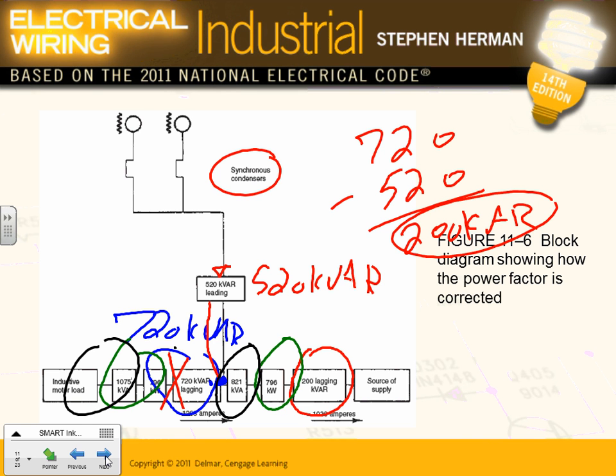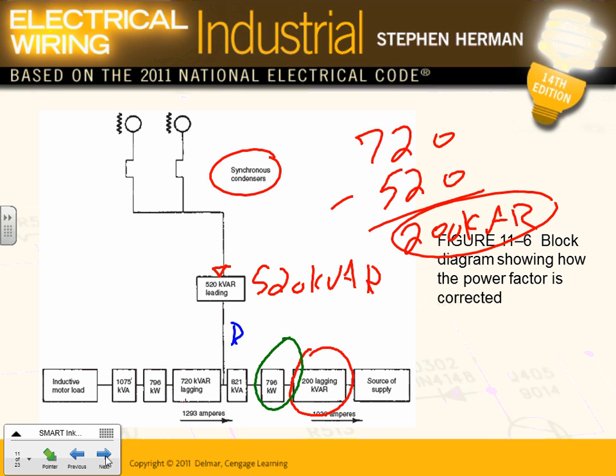So that's how they tie them right in here, into the power system, and they correct your power factor. They knock down your kVAR. They don't do anything to your kilowatt hour or kilowatt. Your true power stays the same. The only thing that they deal with is they knock down your kVAR. I just want to emphasize one little thing here. They don't increase or decrease your kilowatt hour. You don't touch it at all. Their job is to take the bad offenders, kVARs, and reduce them.